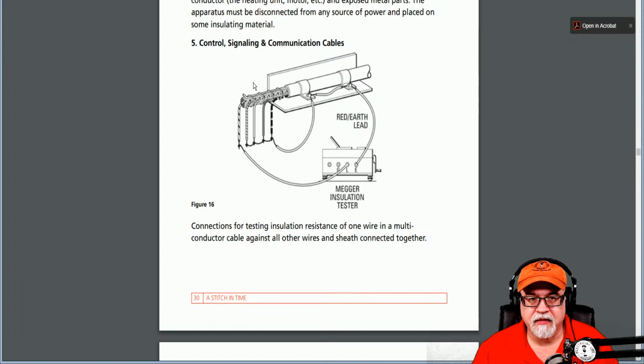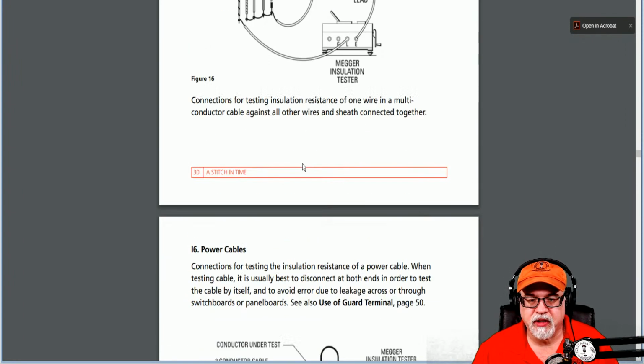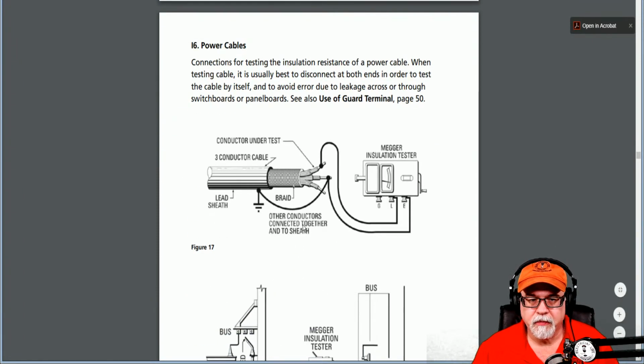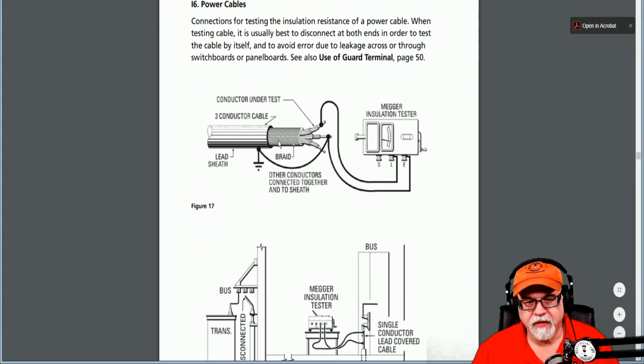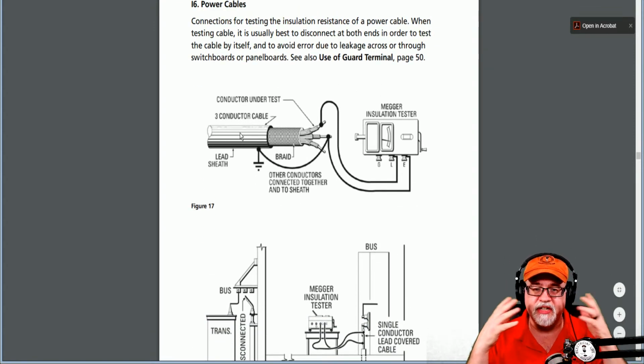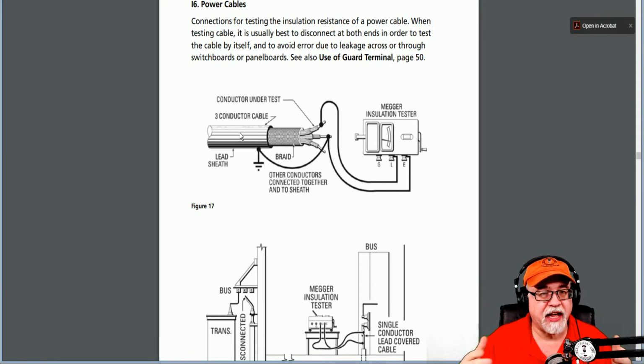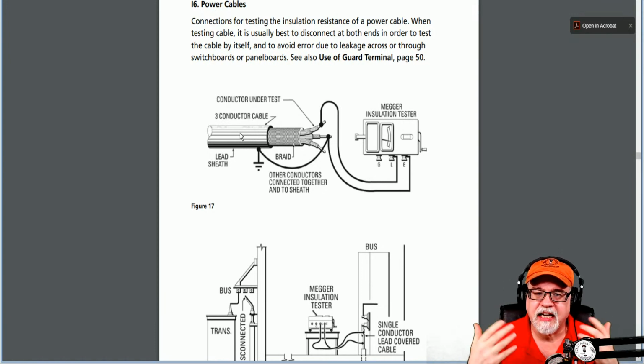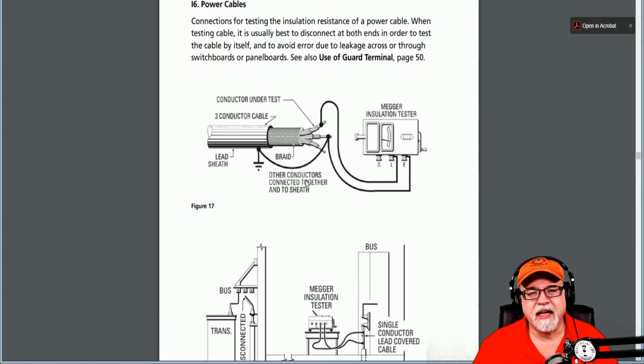And again, showing things like control signaling of communication cables, and then it shows a power cable. Now, even in their own document, they show that the actual outer sheathing is lead sheathing. Of course, that could be EMT tubing, that could be rigid or whatever. Notice it's not non-metallic. So in order to get a good reading, you'll notice that you test one conductor under test, and you take the 3 other cables, okay, and you connect them to the sheathing that's metal. Why? Because anything that would leak here comes back on a return path, okay?